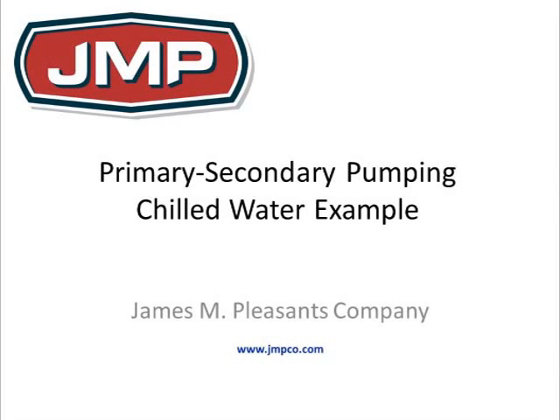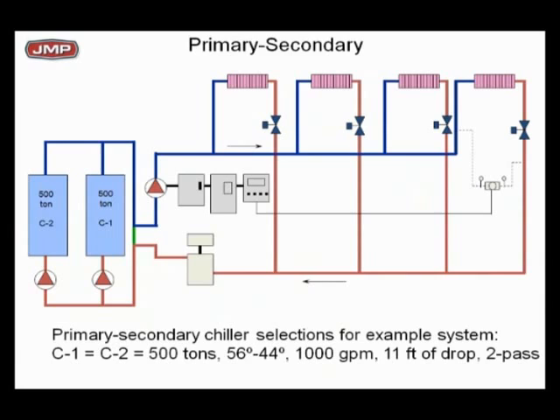Let's look at a real-world application of primary, secondary, and try to get some of these concepts to you a little higher level now, involving primary, secondary, what happens in a loop. I've got two 500-ton chillers here. Let's make them 12 degrees delta T on the chill water side. I like 12 degrees because it's 2 GPM per ton. So this system could make, with the first chiller, 1,000 GPM, second chiller online, 2,000 GPM. Designed as constant flow chillers, chiller 1 and chiller 2.